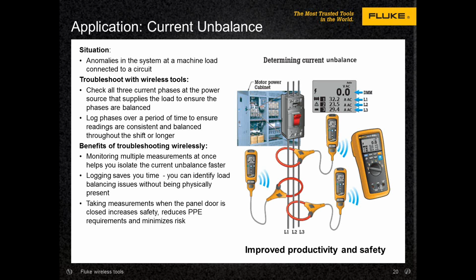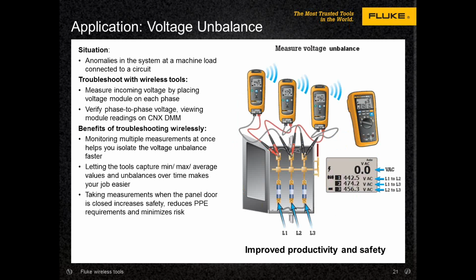Well, anybody that's used to doing this kind of thing, if you had 3 of those flex clamps or 3 of those hard jaw clamps around 3 conductors, you're going to see those 3 current readings in that display at the same time, and you're immediately going to know whether you have an issue. So it's another time saver. Voltage unbalance is very similar to current unbalance.